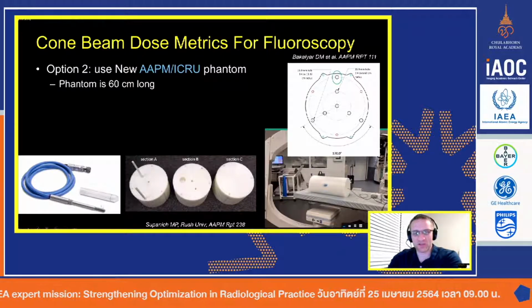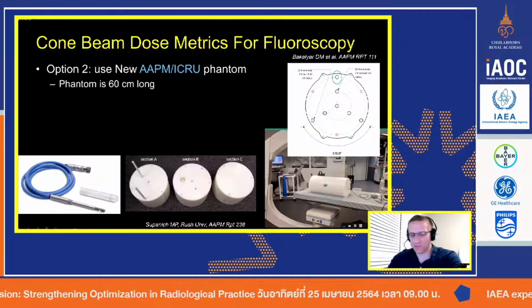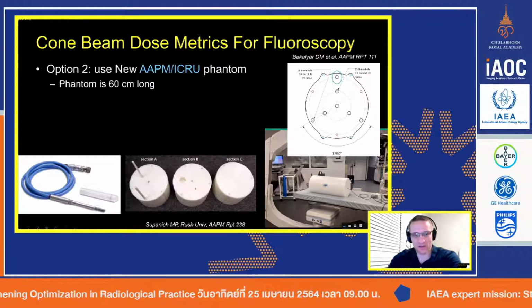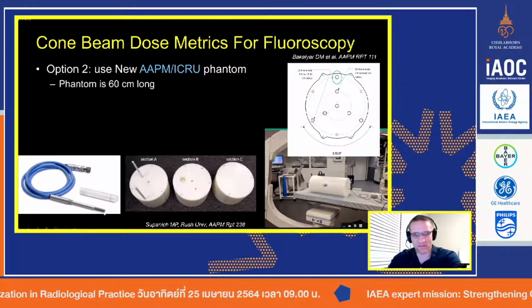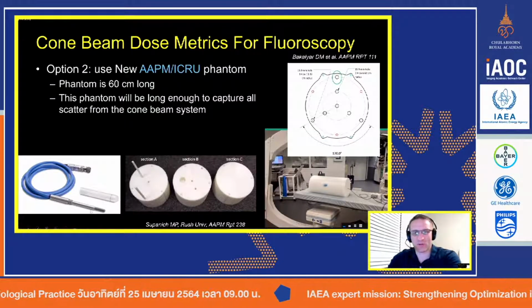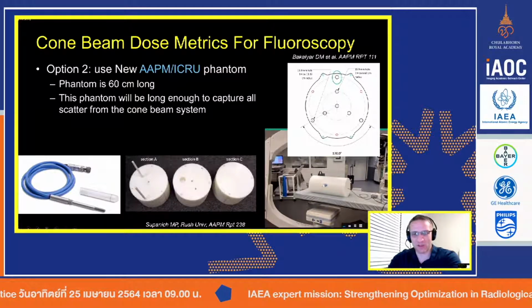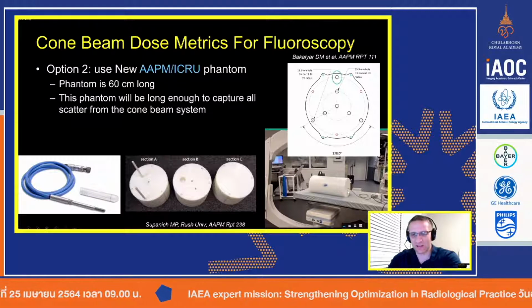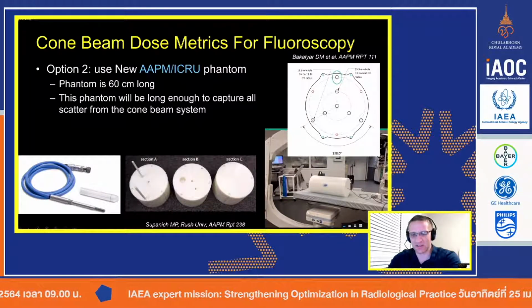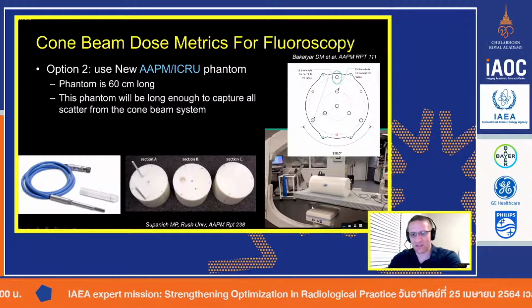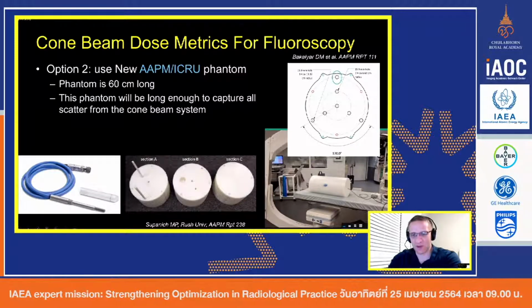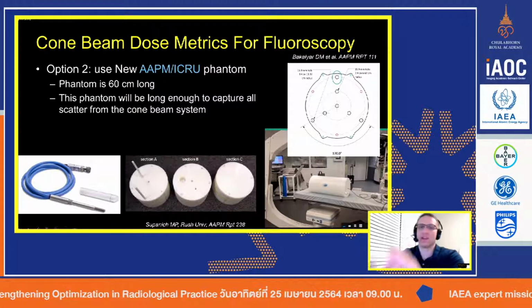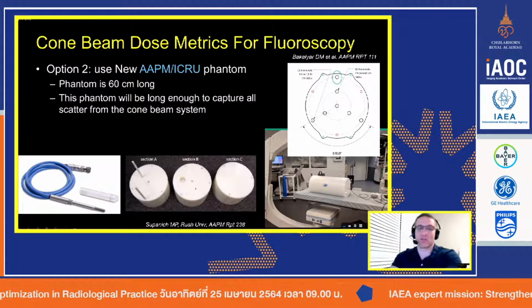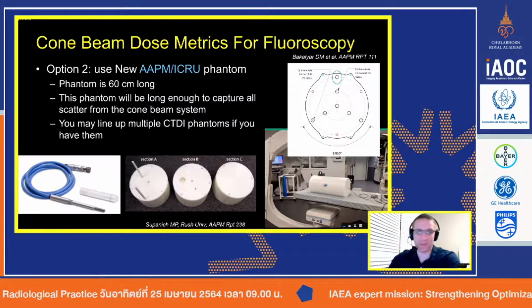We're going to still use the same phantom, ion chamber, the pencil chamber, the Farmer chamber, and that will allow us to make sample measurements along this entire length. Now here you go, you can see the detector is actually on the bottom. And so this detector, you can see, is obviously smaller now than the phantom. So in this case, we'll actually be able to capture all of the scatter. So we're getting better now.